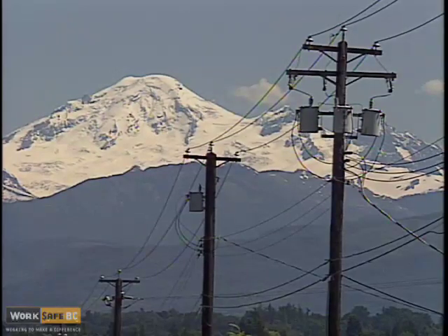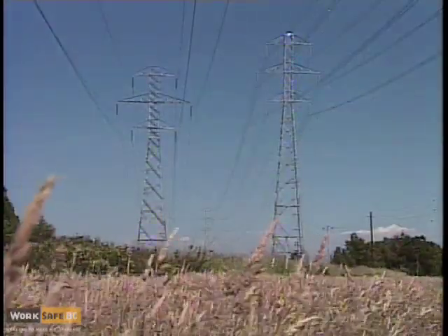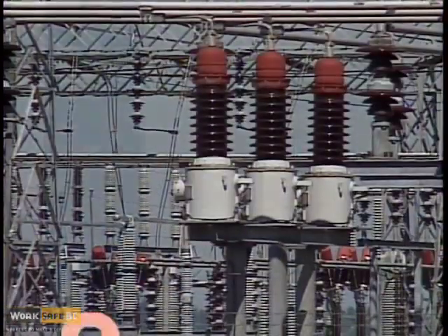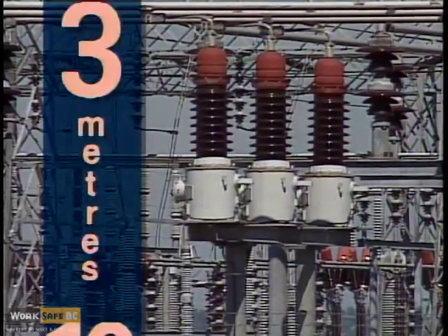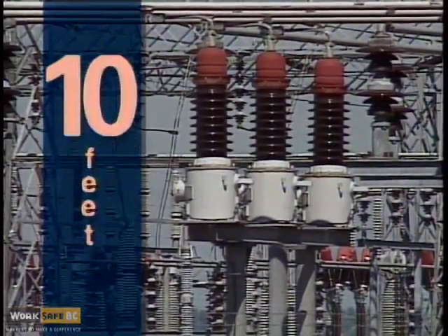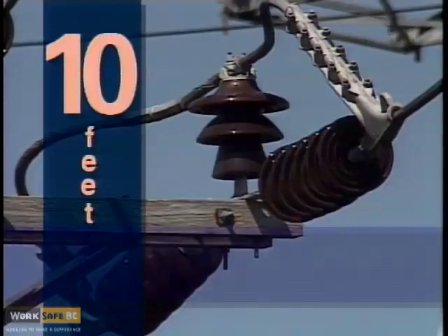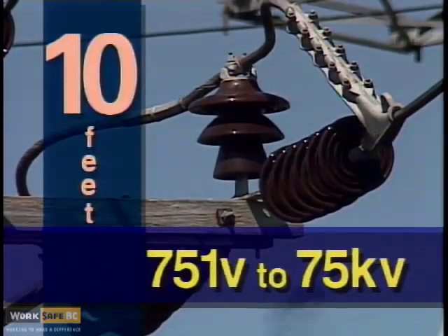WCB regulations state the minimum distances that must be maintained from high voltage lines for personnel, material, equipment, and machinery are 3 meters or 10 feet. This applies to lines carrying 751 volts to 75,000 volts.